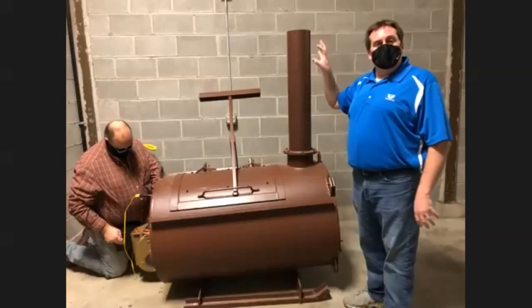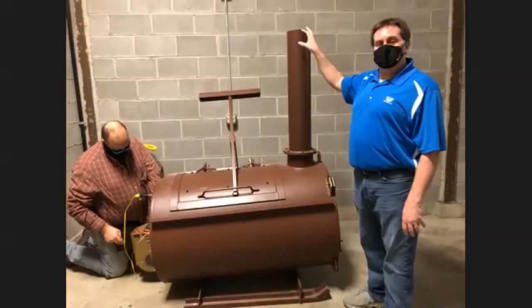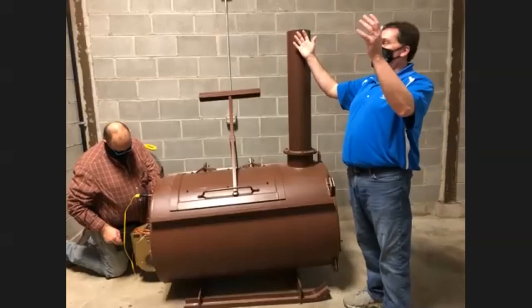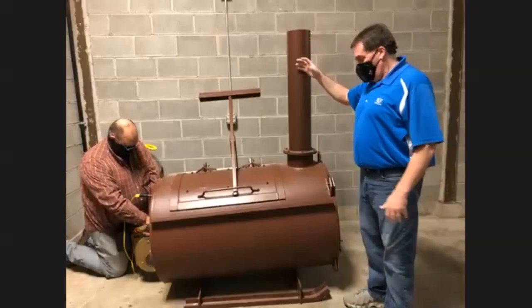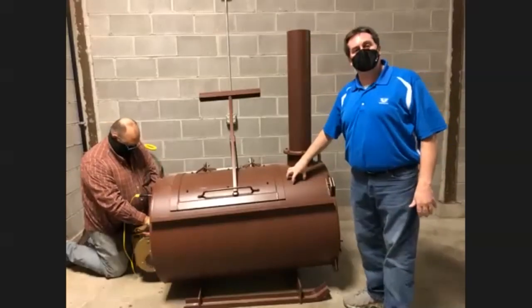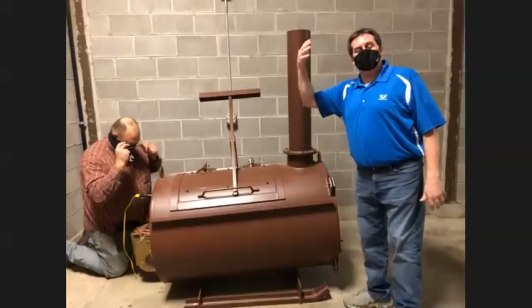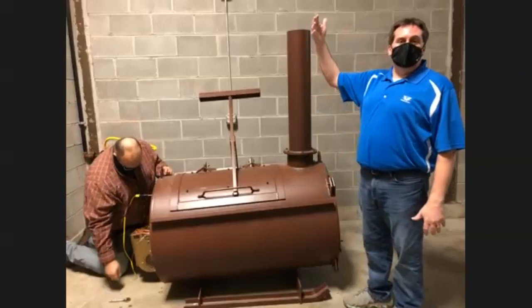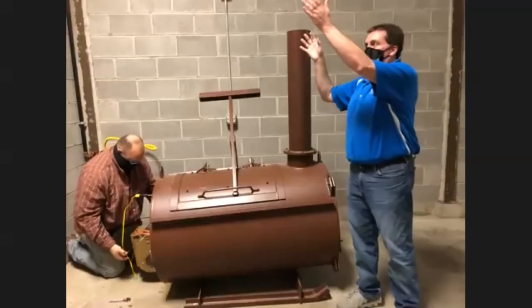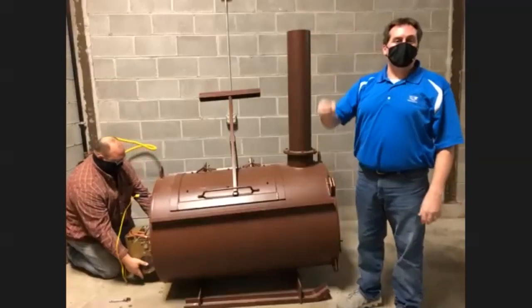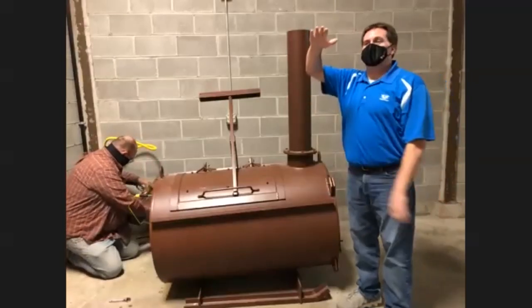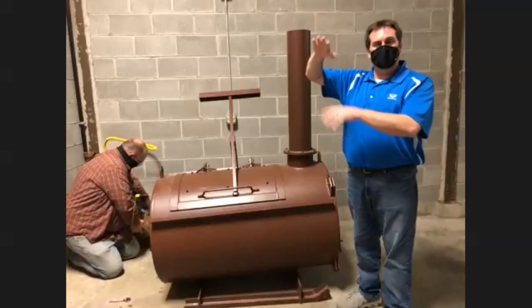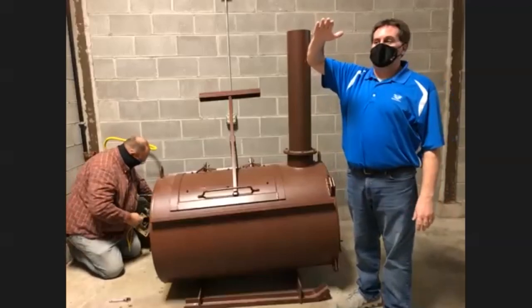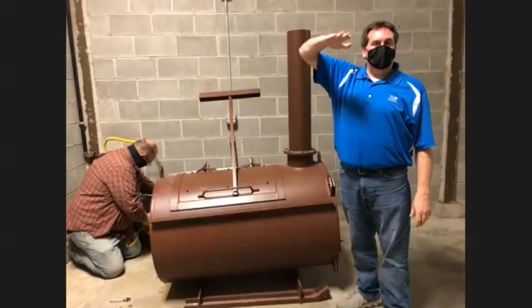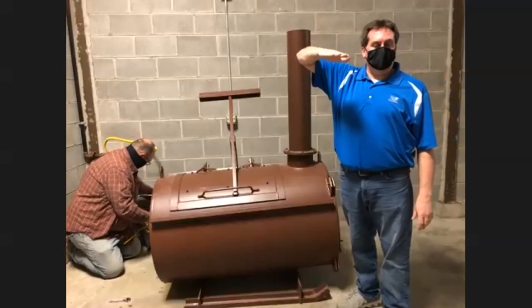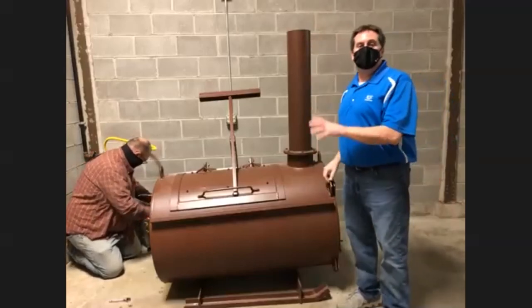Again, when I recommend a secondary burner, the model 20, any afterburner or secondary burner is going to be set up perpendicular to the main unit. So it's going to be set 90 degrees. The model 20 units are large enough, they hang out enough where you actually have a support rod. You must have that adjusted properly according to what it says in the manual. If you do not have that support rod, your secondary burner may hang low and cause issues. You want to make sure you put that support rod in there properly.